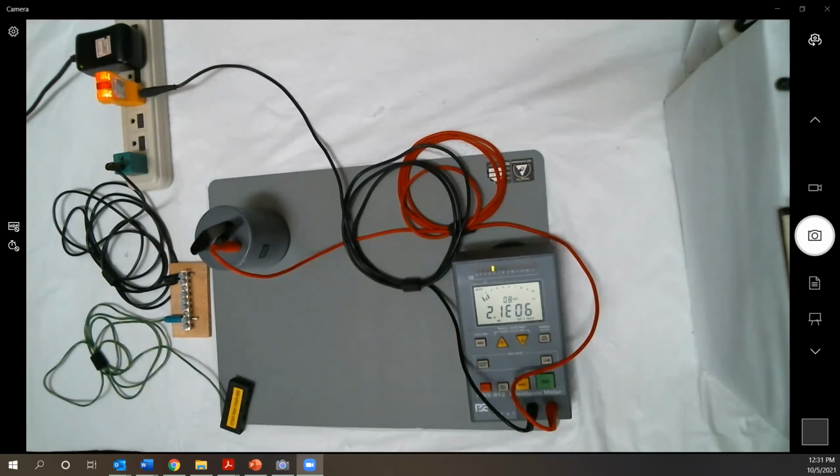Well, I guess the reason for not testing at 100 first is that you don't want to connect 100 volts to a low impedance circuit. It wouldn't damage anything, it would just load it down, but it's probably not the best thing to do for your equipment. It's always better to start low, verify that your resistance is greater than 1 megaohm, and then switch to the 100 volts.